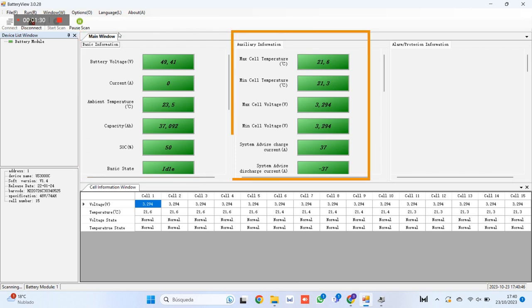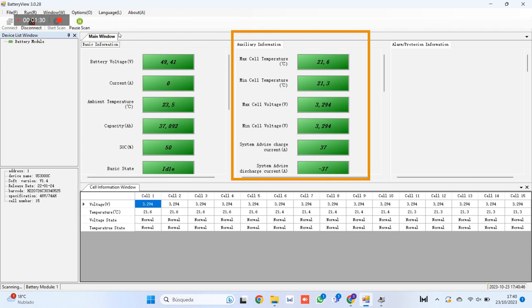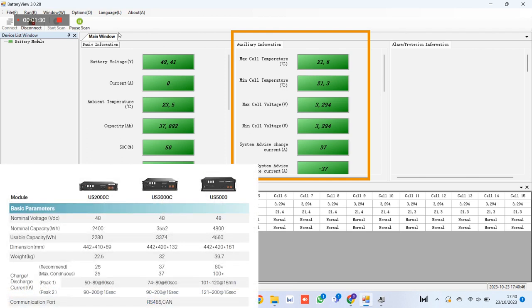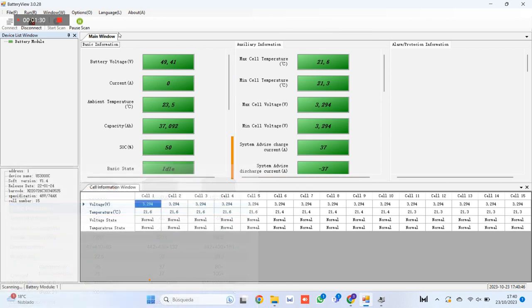Section 3, auxiliary information, it can be observed how the maximum temperature of the cells is 21.6 degrees centigrade and the minimum temperature is 21.3. The maximum and minimum voltage of the cells is 3.294 volts. And finally, it is observed how this battery has limited the charge and discharge current to 37 amperes, as it marks its technical data sheet.